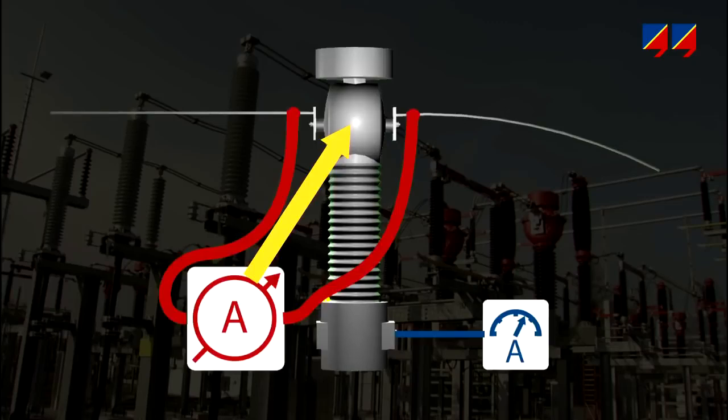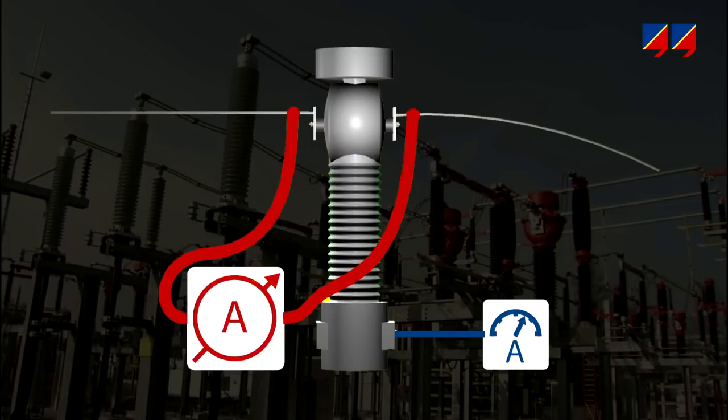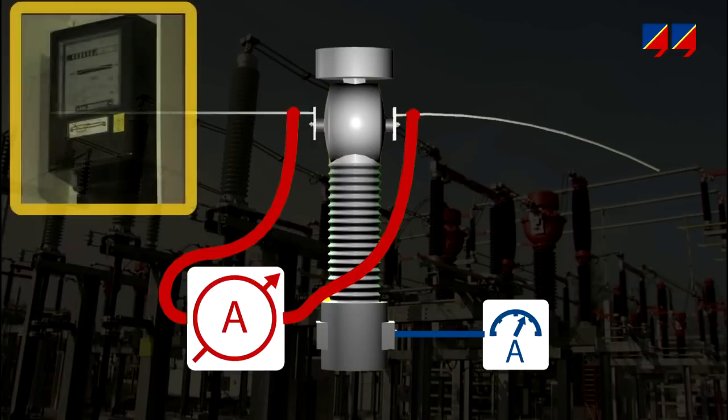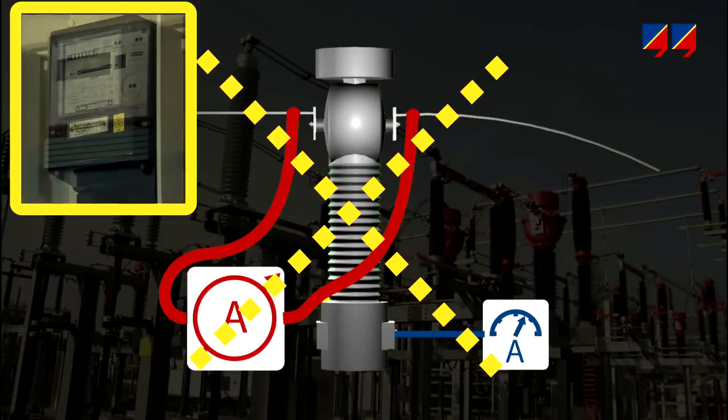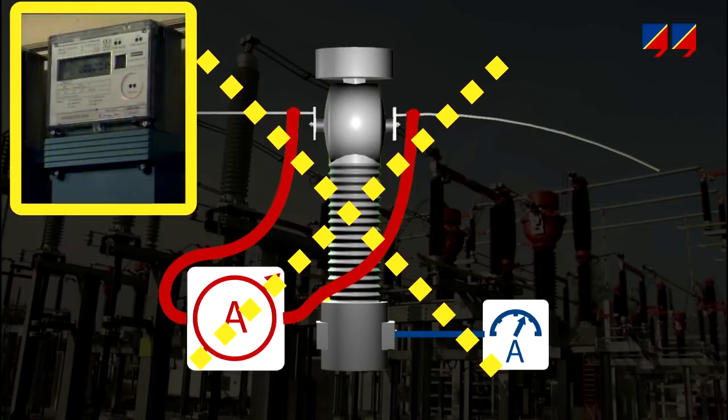Injecting current on the primary side using a portable high-current source and measuring secondary current allows the ratio and wiring of a particular core and tap to be checked. This method is insufficient, particularly for verifying metering CTs, because of limitations in the current amplitude, limited accuracy, and the inability to consider different burden values.